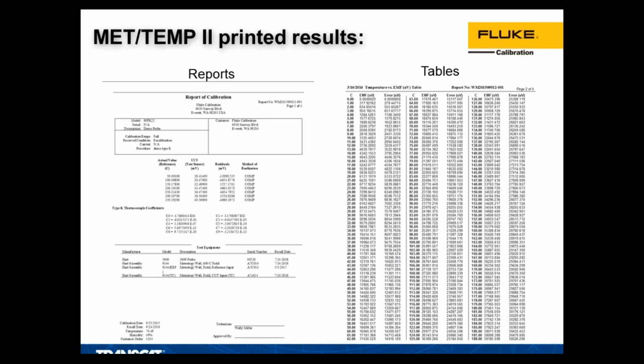The reports look like this, and there's some customization you can do, but it'll put in the model and serial number, your address, whatever you need. In addition to the results of your calibration, it'll indicate what the actual values were, what the unit under test read, and it'll indicate the residuals.